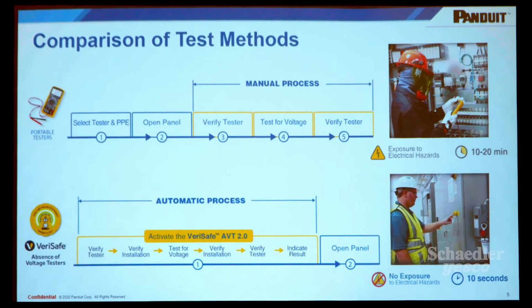So here's a comparison. Basically, it automates a large portion of the live, dead, live test. At the top is your traditional live, dead, live test. You've got to throw your breaker. You still do that, obviously. You've got to suit up in your PPE. You've got to go get your test device. Then you've got to go open up the panel and do your live, dead, live test, which is very manual. It can take 10 to 20 minutes, depending on the application and the machinery that you're testing. The AVT basically automates a large portion of that in about 10 seconds.